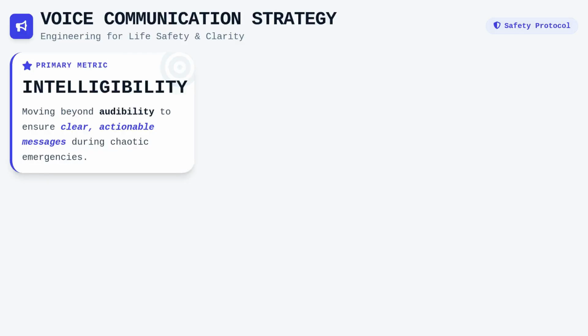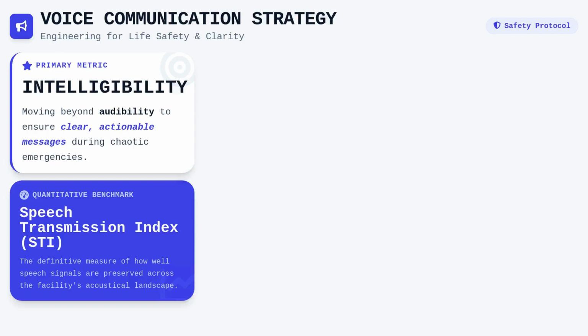Intelligibility is the primary metric by which we evaluate the success of our voice communication strategy. It is not enough to simply have an audible signal. We need a clear, actionable message that reaches the occupant, even amidst the chaotic noise of an unfolding emergency. We utilize the Speech Transmission Index as our quantitative benchmark for this clarity, measuring the degree to which speech signals are preserved across the acoustical landscape of the facility.